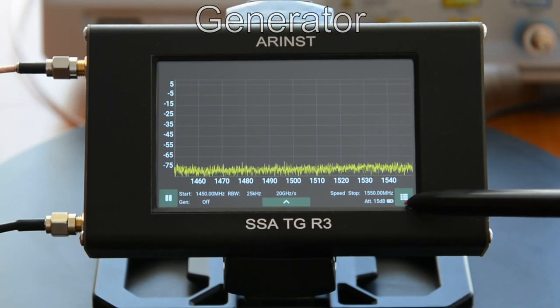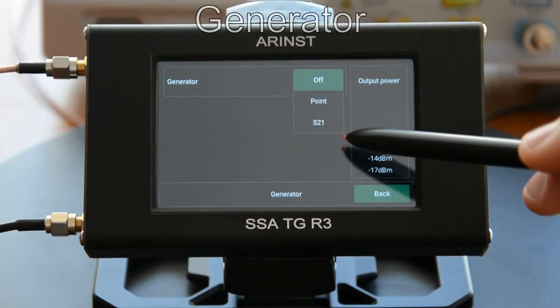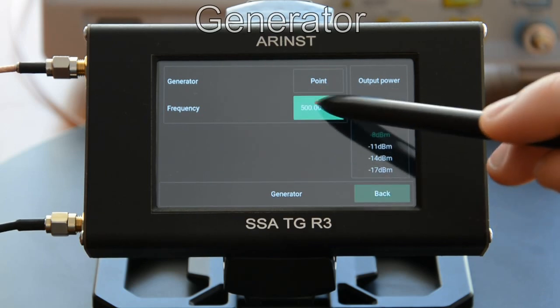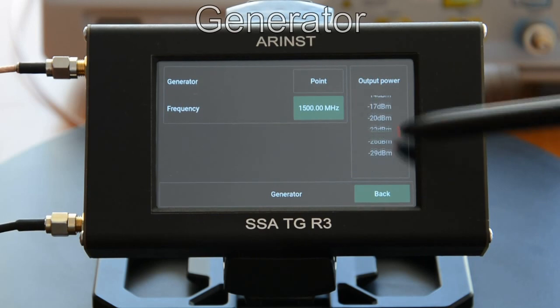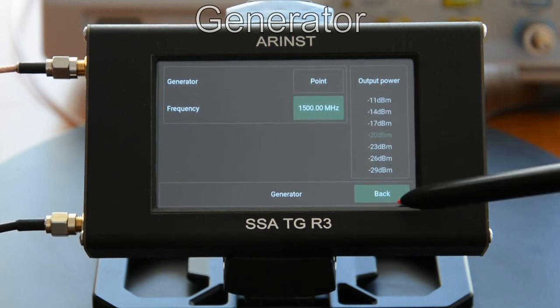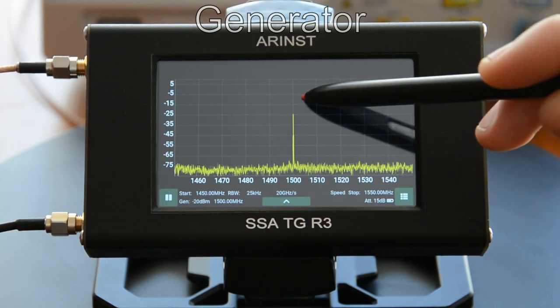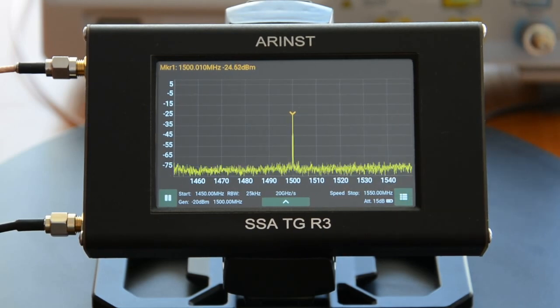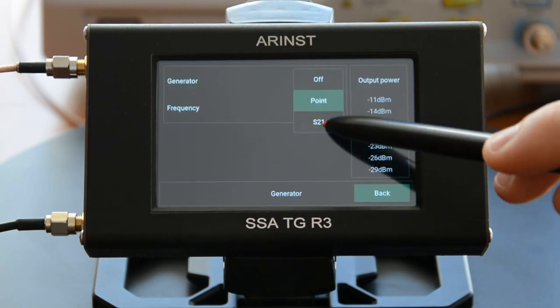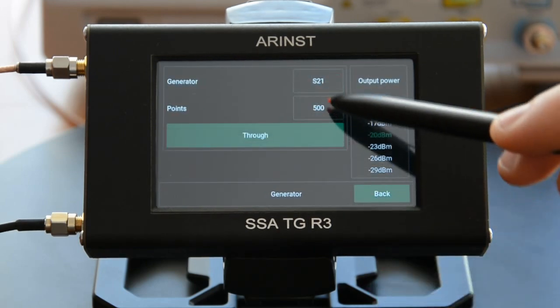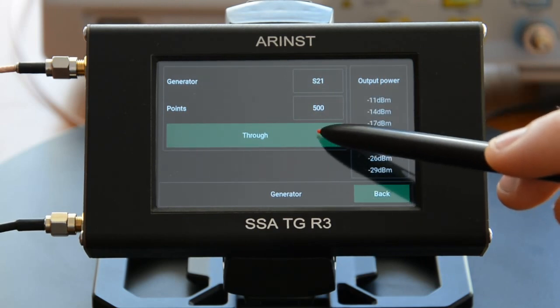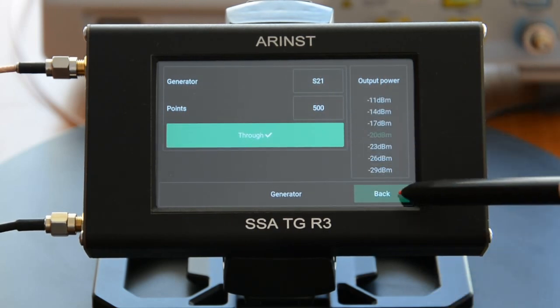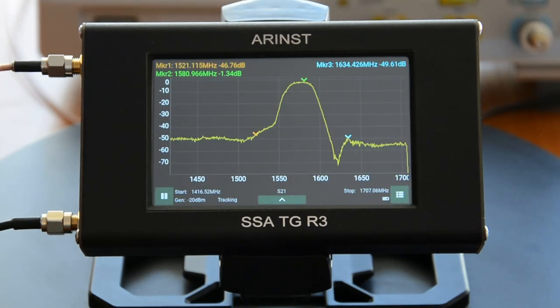Working with the generator in fixed frequency mode. Working with the generator in tracking mode to measure the transmission coefficient: connect the generator output and the analyzer input with a jumper and calibrate. After calibration, connect the device under test instead of the jumper.